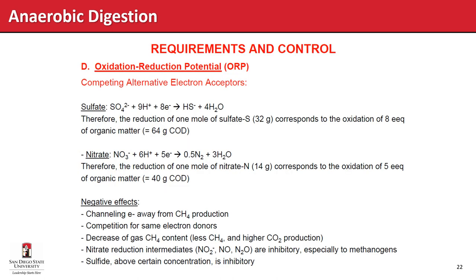Oxidation reduction potential (ORP) tells us how reducing conditions are in the digester. Compounds like sulfate or nitrate raise the ORP and can inhibit anaerobic digestion — they channel electrons away from methane production toward nitrate and sulfate reduction, decreasing methane content in the gas. Some intermediates can be inhibitory, and sulfide itself is inhibitory, so excessive sulfate reduction can lead to inhibitory concentrations.